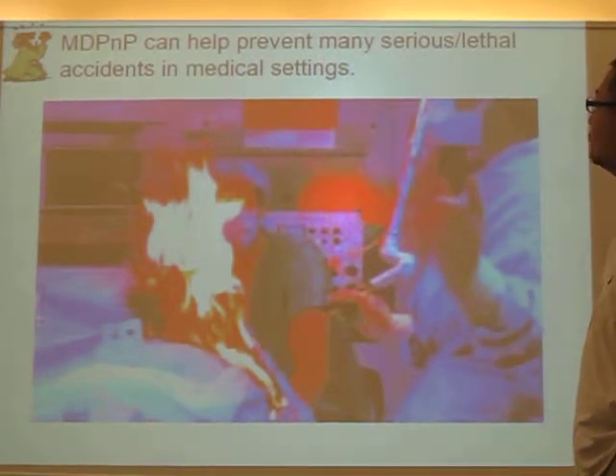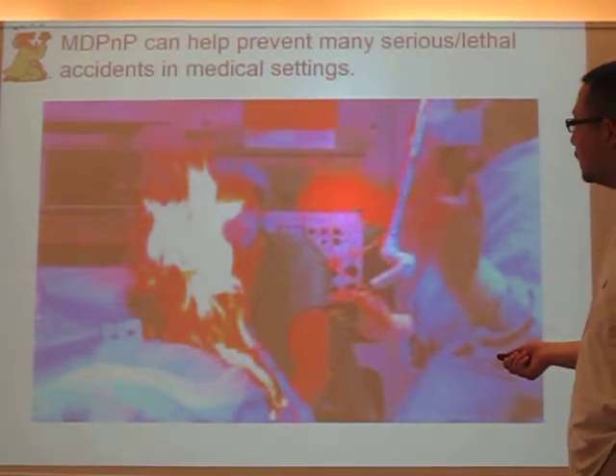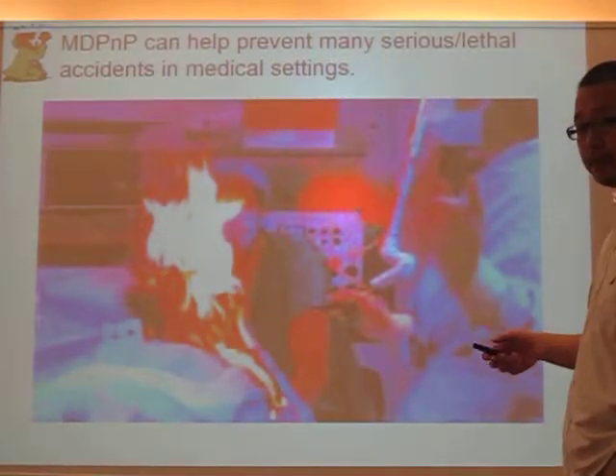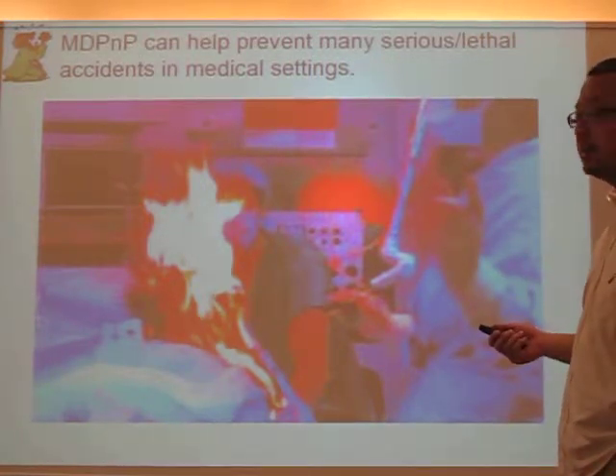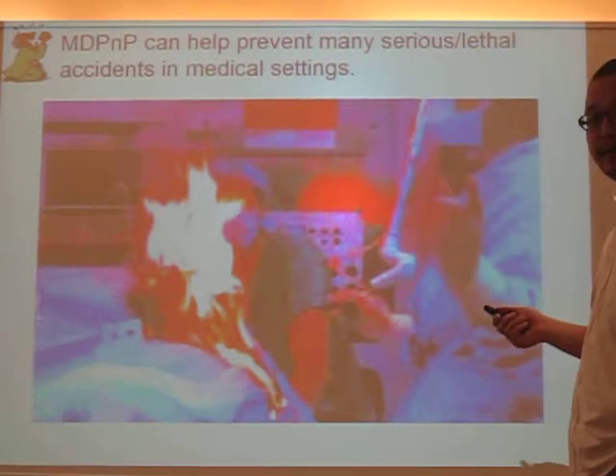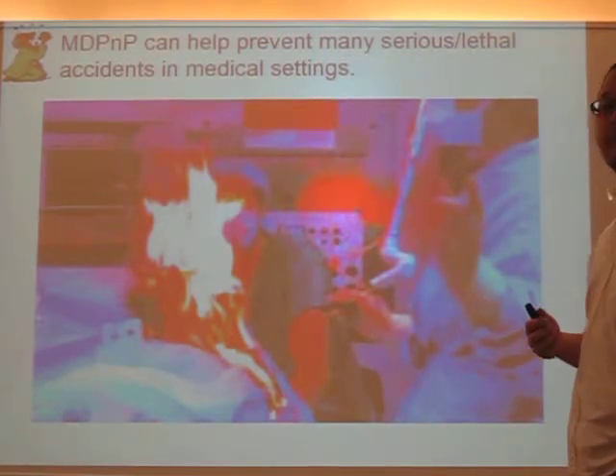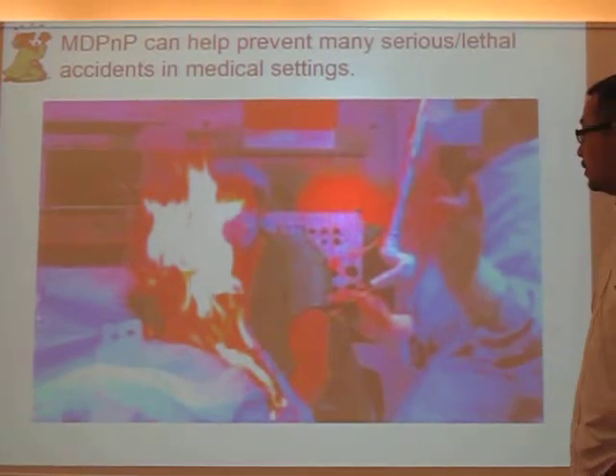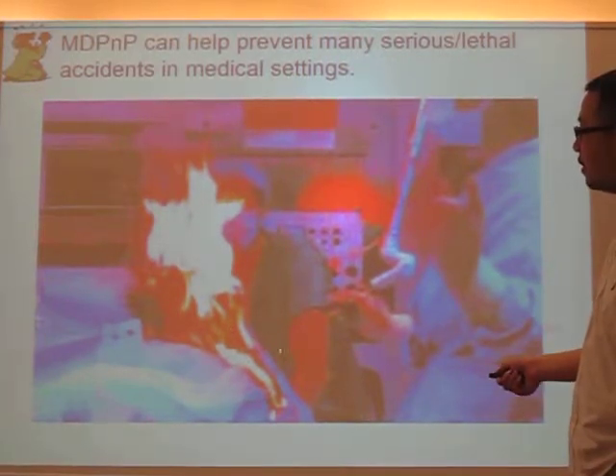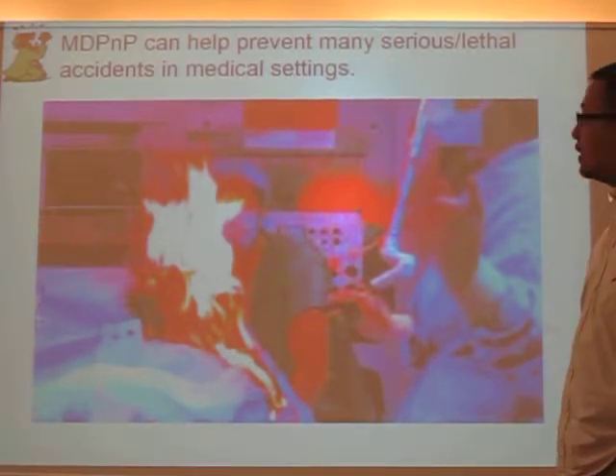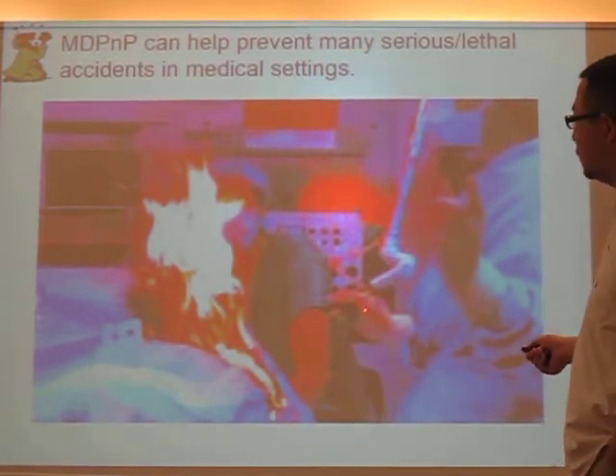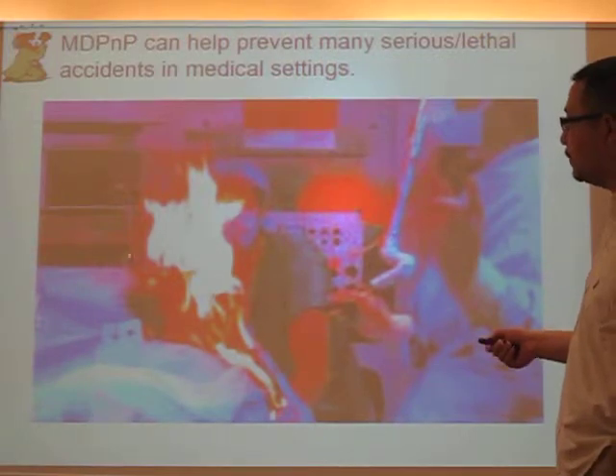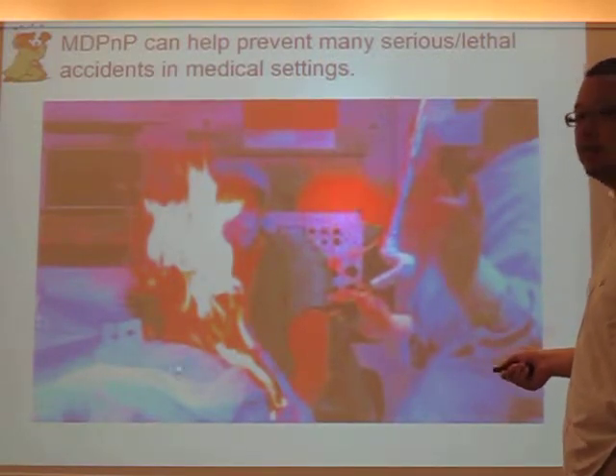MDPnP can help prevent many serious lethal accidents in medical settings. For example, if we are using a laser scalpel to do laser tracheotomy, one kind of accident that can happen is that when you cut the windpipe using laser and inside the windpipe there is a high concentration of oxygen, you can actually set fire on the patient. So MDPnP's job in laser tracheotomy is to interlock the laser scalpel with the ventilator to prevent this kind of situation from happening.